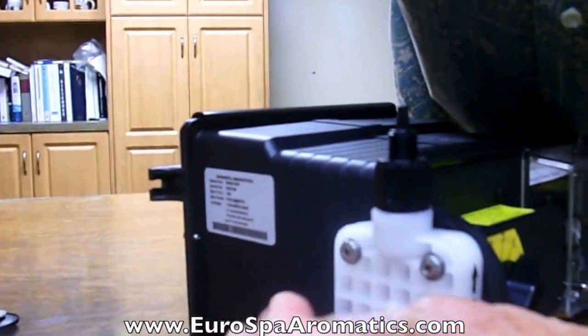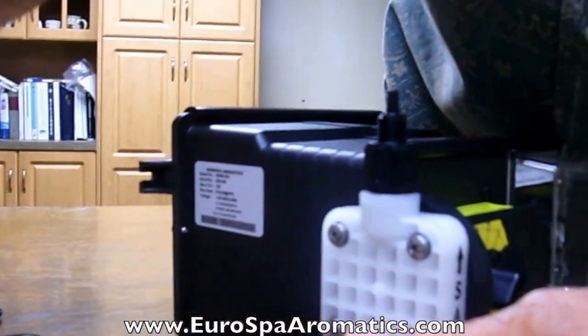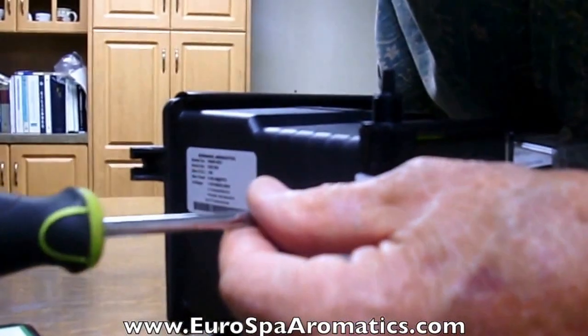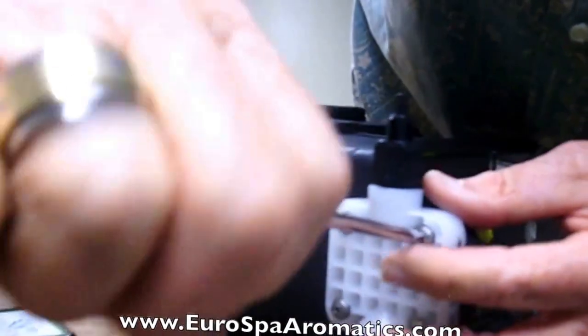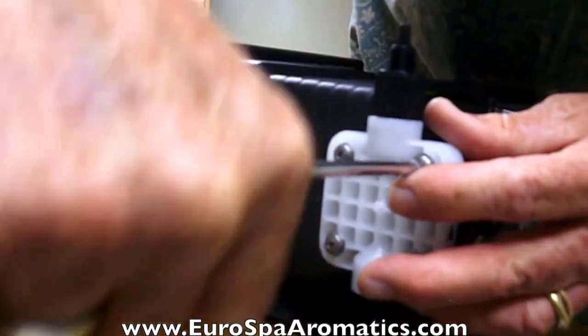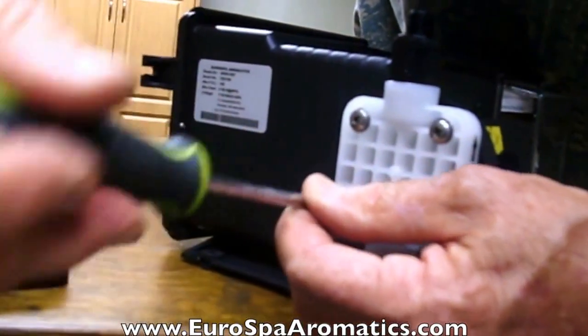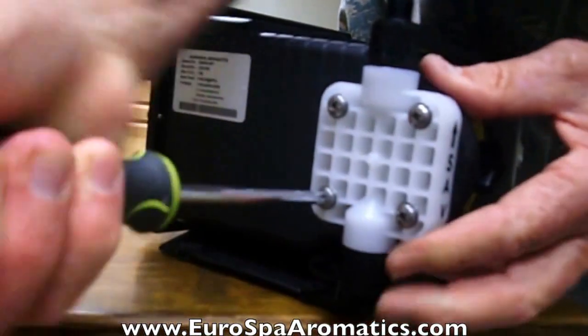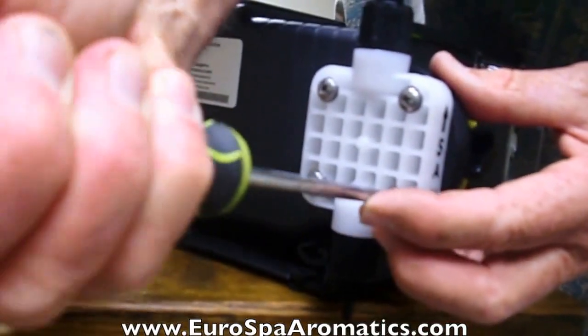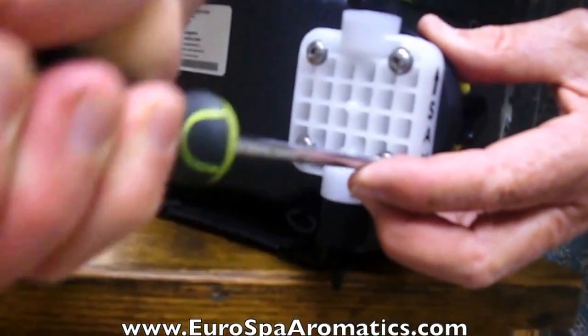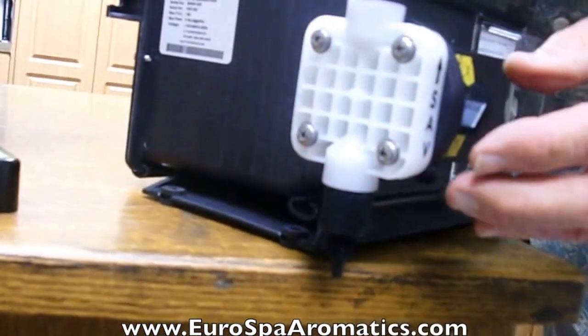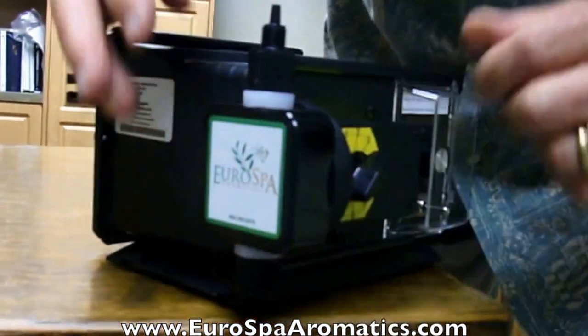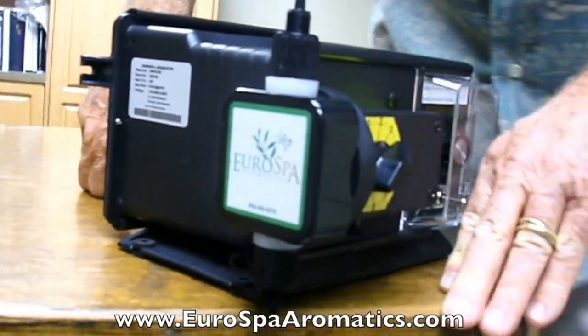So you snug down opposite corners. And again, they don't need to come down real tight, just tight enough to where you get a good seal between the head and the housing, the pump body itself. Snap the cap back on, and you've replaced your diaphragm. Now you have another 2 to 3 years before you'll need to do that operation.